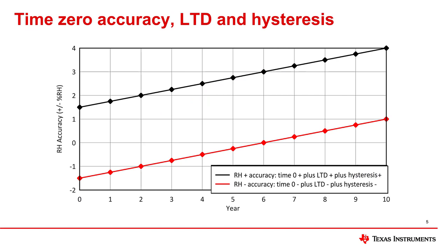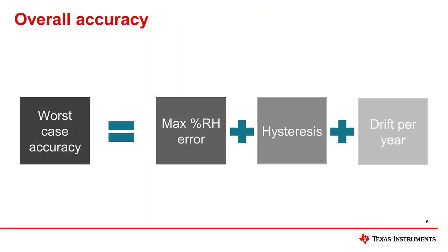This graph illustrates how long-term drift and hysteresis add on to the time zero accuracy as the lifetime of the part increases. A sensor's overall humidity accuracy is a combination of maximum percentage error, hysteresis, and long-term drift per year.